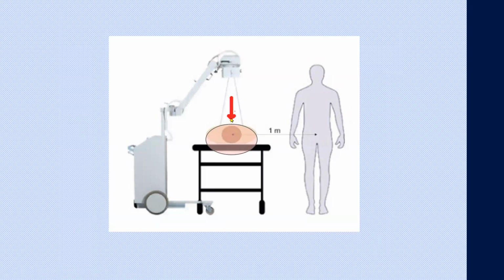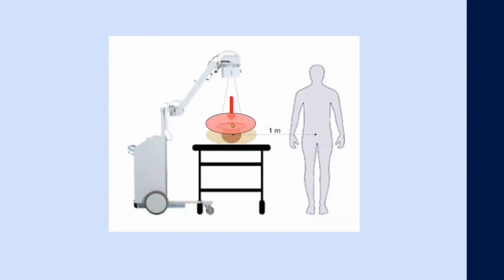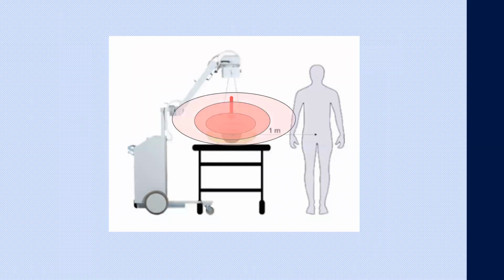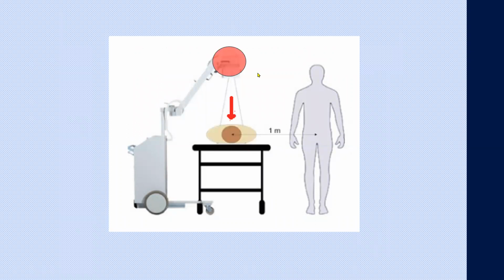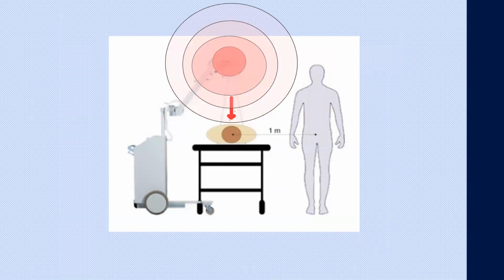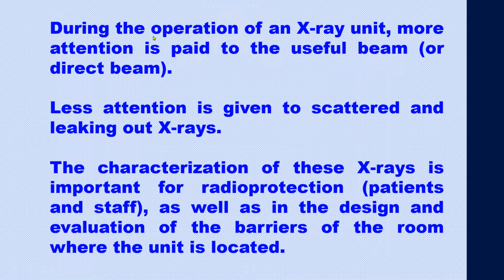When this main beam collides with the body, some photons will be scattered out, reaching other parts of the room, and there will also be another set of photons that leak out from the X-ray tube head. So these scattered and leaked photons also reach other parts of the room. During the operation of an X-ray unit, more attention is paid to the useful beam or direct beam, but much less attention is given to these scattered and leaking X-rays.